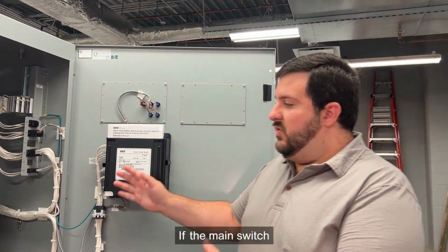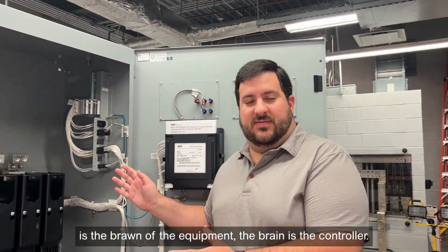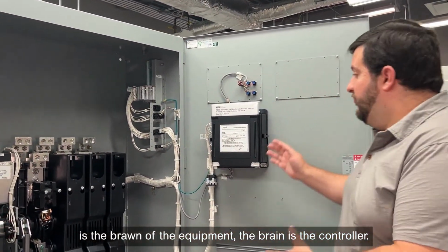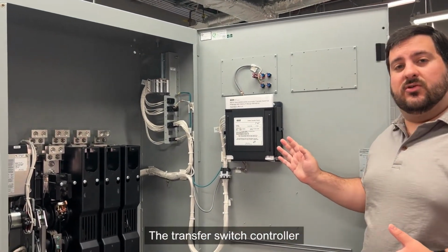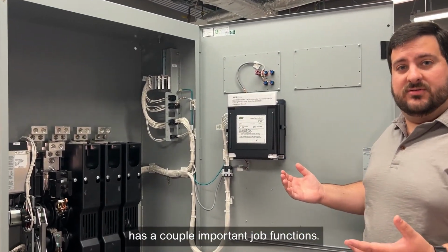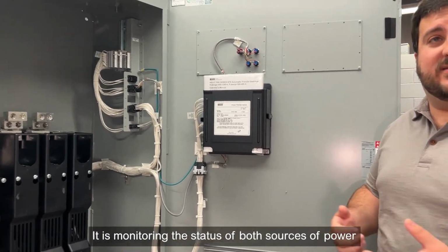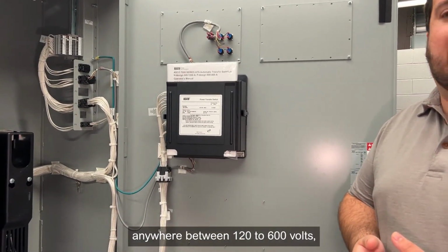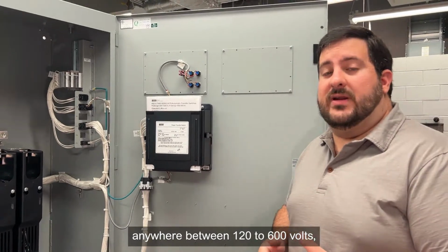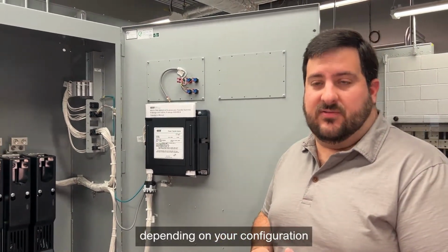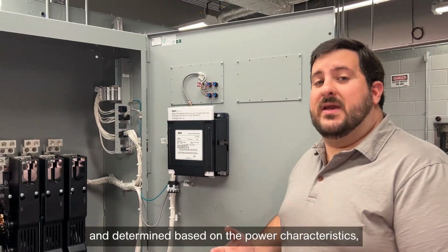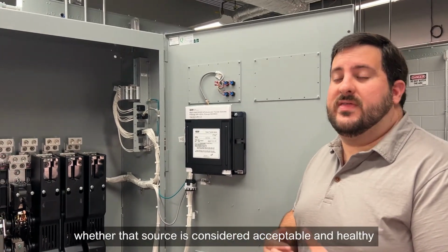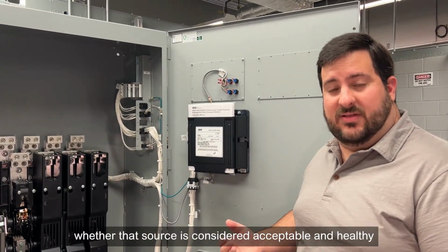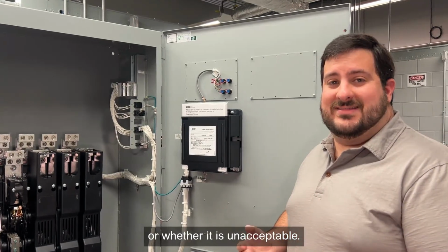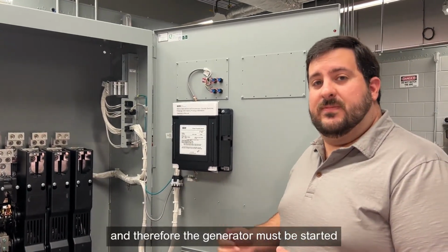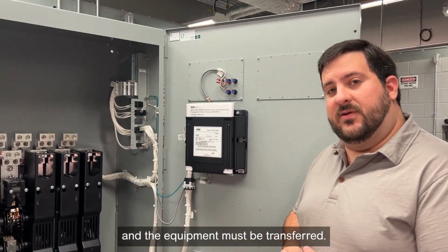If the main switch is the brawn of the equipment, the brain is the controller. The transfer switch controller has a couple important job functions. It is monitoring the status of both sources of power, anywhere between 120 to 600 volts, depending on your configuration. It determines, based on the power characteristics, whether that source is considered acceptable and healthy, or whether it is unacceptable, and therefore the generator must be started and the equipment must be transferred.